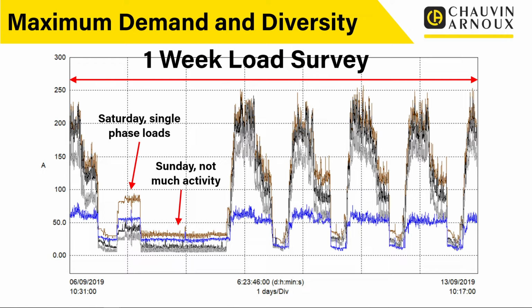So when we talk more about energy efficiency, actually this is a useful activity for that as well. So then we move on, and you can see the actual characteristics of each individual day there, the start of the day, the way the day looks and the end of it. And obviously, if we're talking about maximum demand, just a basic survey like this would give us a bit of information, because say this was a 100 amp 3-phase supply, and we look at this, we'd be thinking, oh my God, this installation's overloaded.